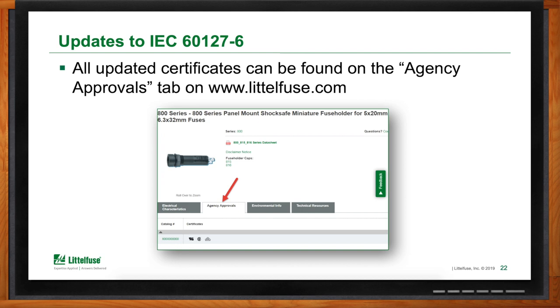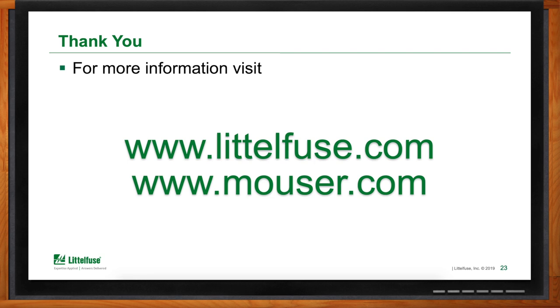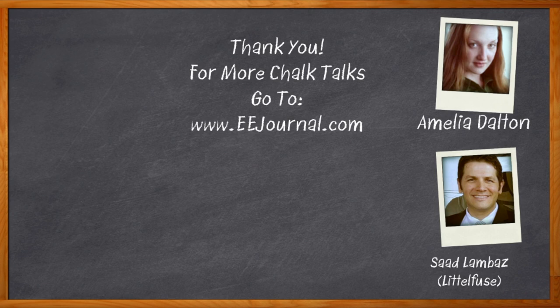Can designers verify that fuse holders have been updated to the latest standards? Yes. The agency we use for approval of these fuse holders is VDE. On the Littelfuse website, if you visit any of the different series mentioned, there is a tab called agency approvals. Once you click on that tab, there is a list of every specific part and its certification. If you click on the VDE symbol, you can see the latest certificate showing the latest edition applied to that particular fuse holder — all showing the second edition of IEC 60127-6. For Chalk Talks, I'm Amelia Dalton from eejournal.com.